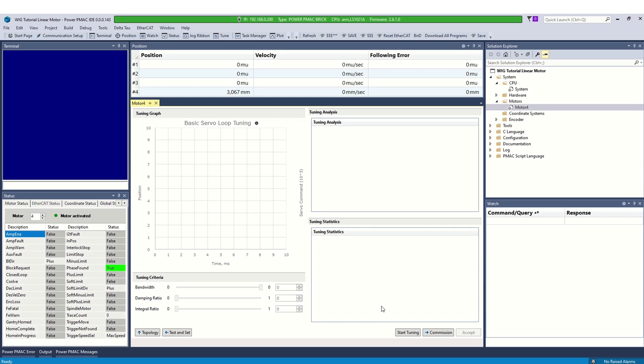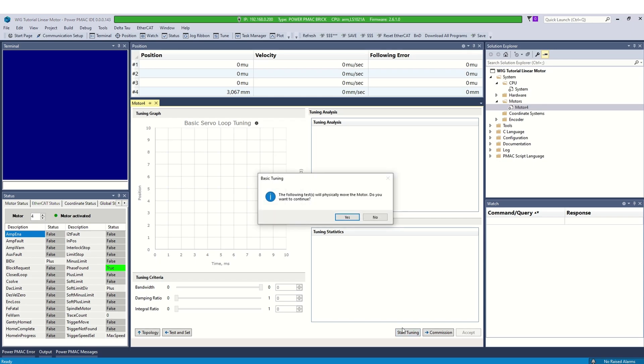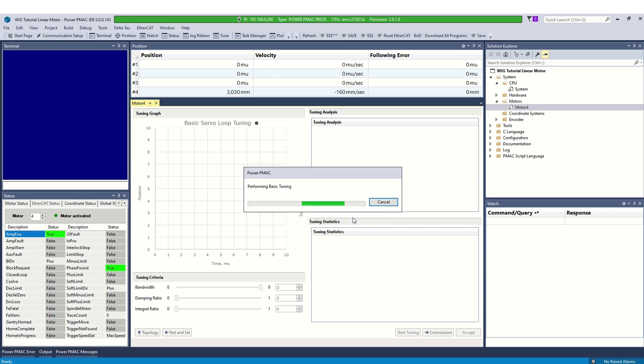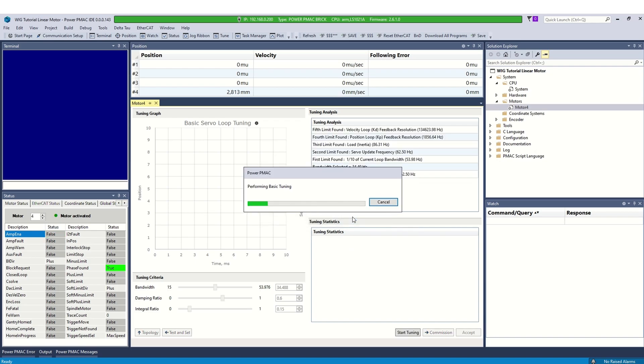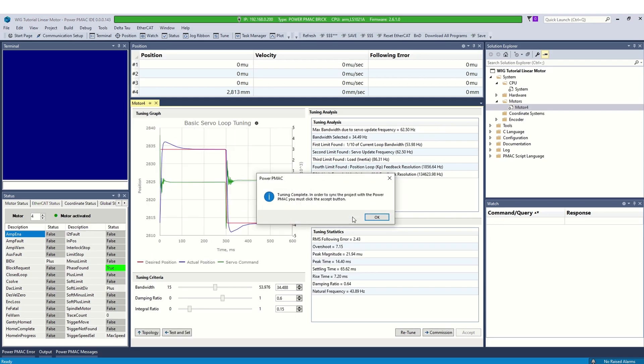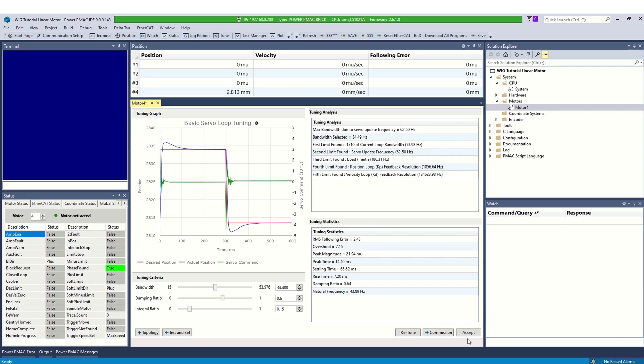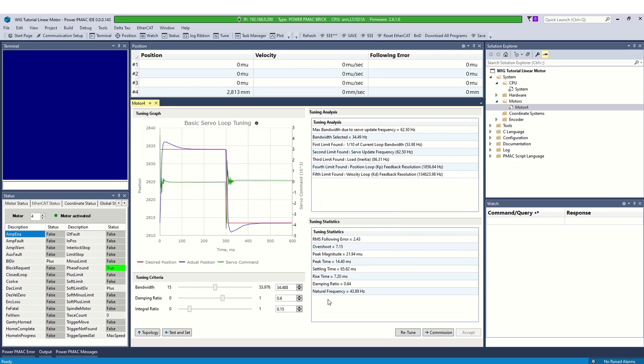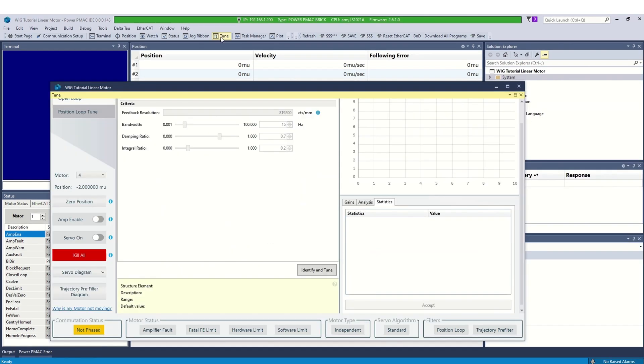Select accept and click on basic tuning. Finally, everything is set up and motor can be tuned using IDE auto-tune feature. This is the basic auto-tune screen which permits a very simple interface for obtaining reasonable servo gains to jog a motor. Click on start tuning. Select yes to perform basic tuning. After the tuning is complete, you will see a plot of the step response and tuning complete message will pop up. Select ok and click accept to synchronize IDE project files with PMAC. If additional tuning is desired, we can always use advanced tuning tool to fine tune the servo gains.